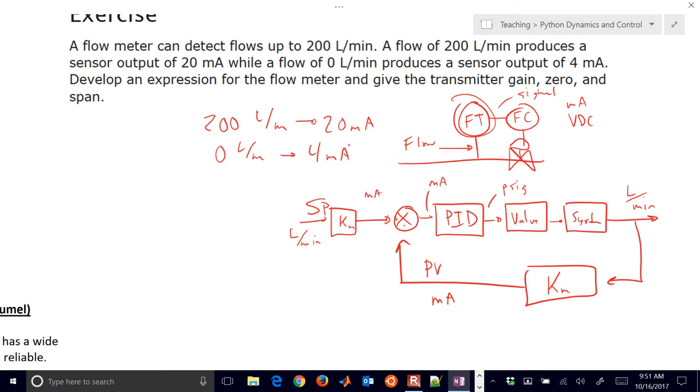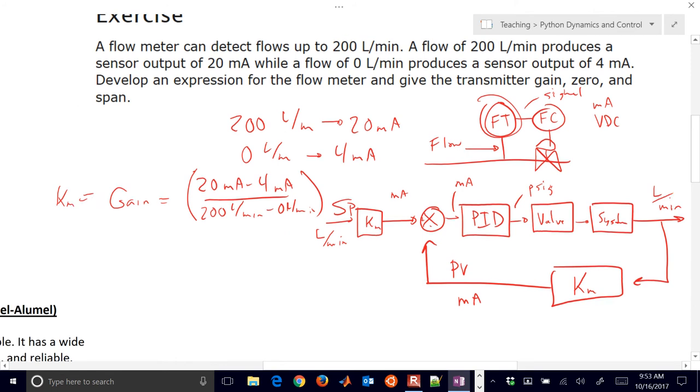So we want to develop an expression for the flow meter and give the transmitter gain, zero, and span. So let's just do the gain first of all. The gain is going to be equal to the, this change, the four to 20 milliamp. So 20 milliamp minus four milliamp divided by 200 liters per minute minus zero liters per minute. So I'm going to take whatever set. So this is going to be our Km value that we calculated there. So let's go ahead and calculate this. Just get a number there. We'll do 20 minus four divided by 200. And that's going to be 0.08. So that has units of milliamps per liters per minute.